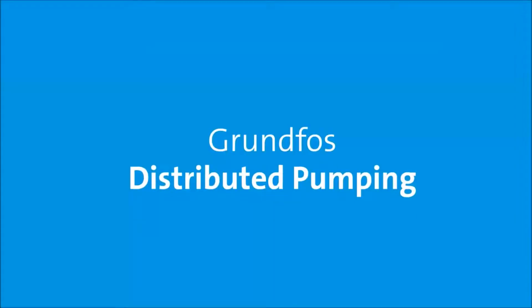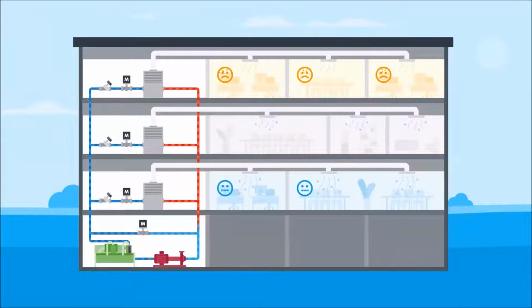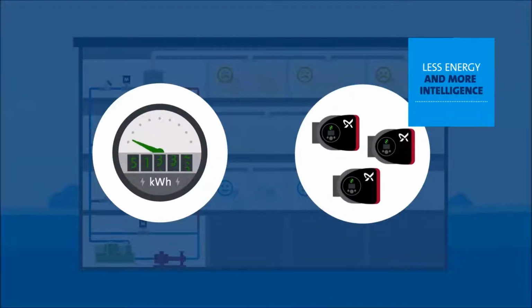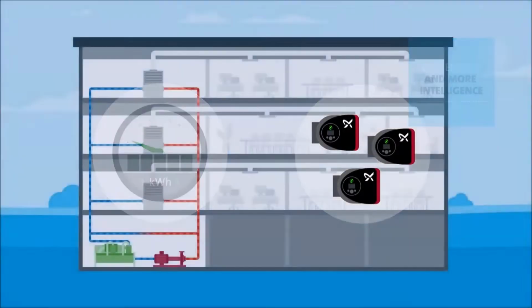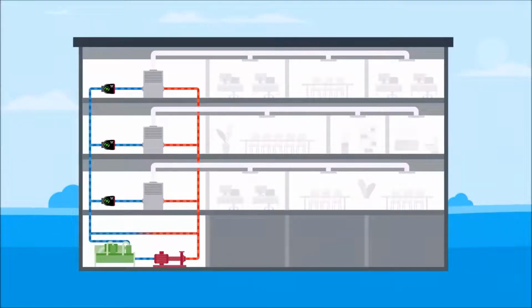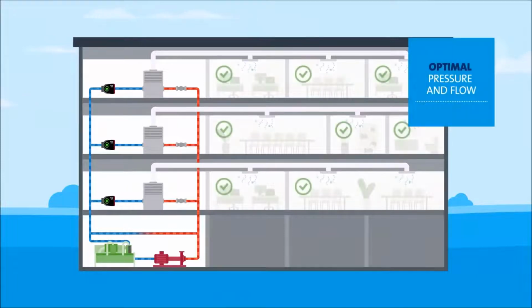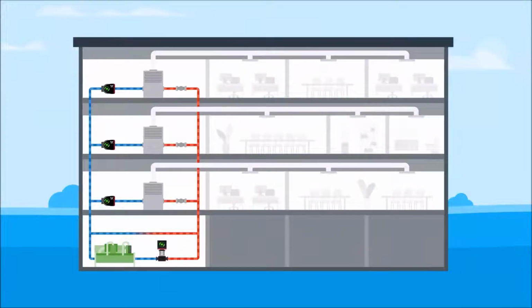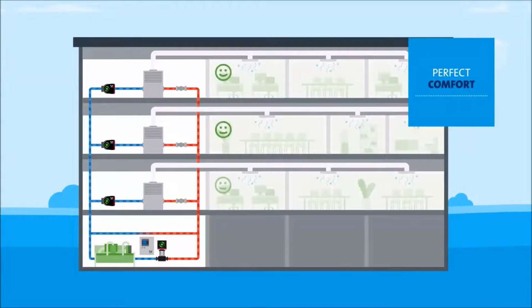Grundfos Distributed Pumping. By replacing valves with intelligent pumps, we use less energy while bringing more intelligence to your cooling system. A Grundfos distributed pumping system uses the maintenance-free Magna 3 circulator and low-pressure non-return valves to prevent backflow. The distributed pumps ensure optimum pressure and flow at each terminal unit at all times. This also allows the centralized pumps managed by a new control logic to be significantly downsized because of the distributed pumps. This new design delivers perfect cooling comfort when and where it is needed within the building.